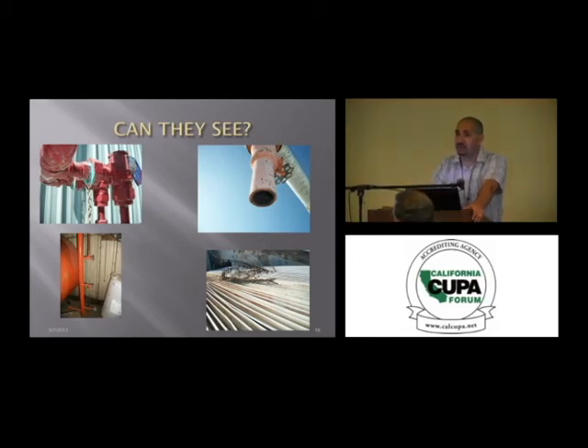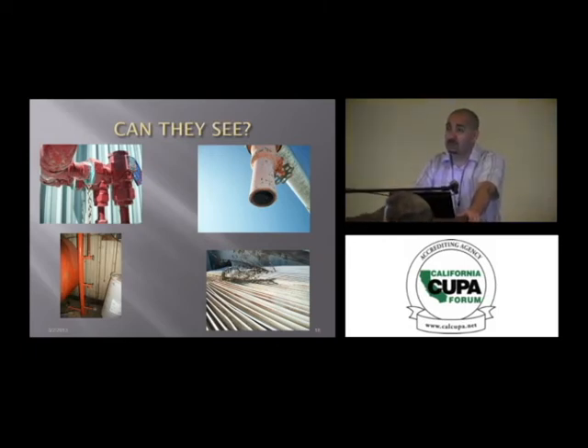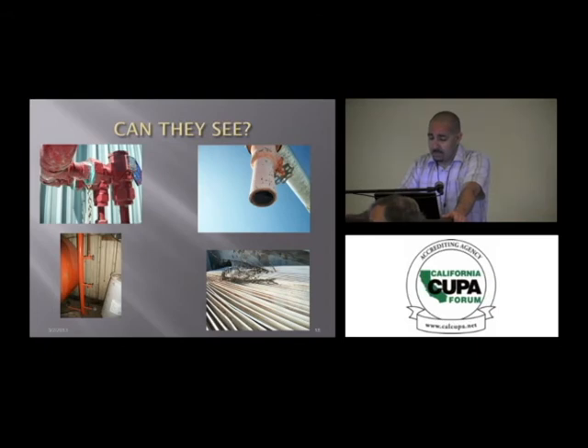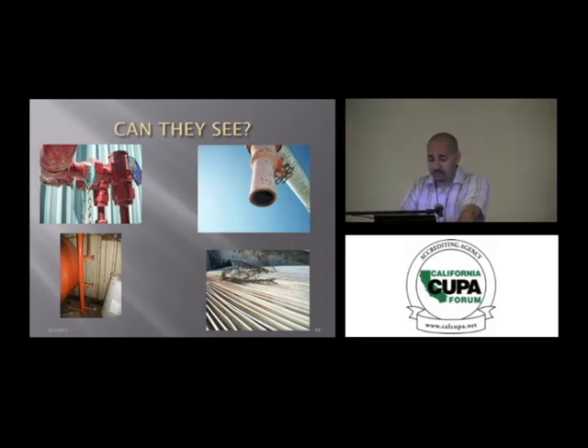To the right-hand side there, again, if I go and I crack open that valve, as you can see, it's not plugged. What's going to come out of there? Ammonia is going to come out of there. Valves need to be plugged, capped, to avoid an inadvertent ammonia release. Yeah, if you're not working on it, it needs to be plugged and capped. To the bottom left-hand side, what's the issue there?